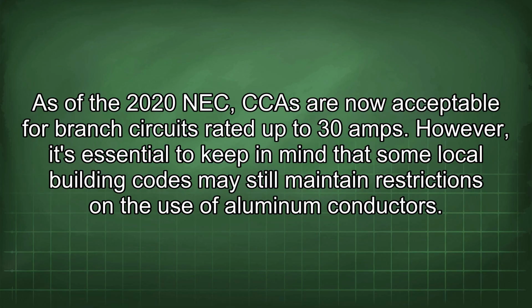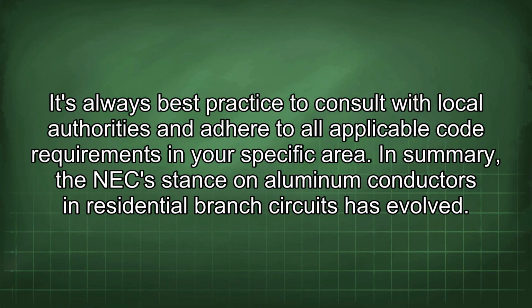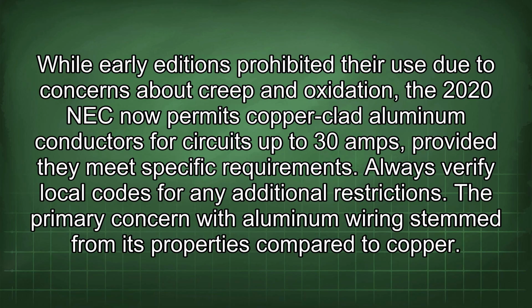However, it's essential to keep in mind that some local building codes may still maintain restrictions on the use of aluminum conductors. It's always best practice to consult with local authorities and adhere to all applicable code requirements in your specific area. In summary, the NEC stance on aluminum conductors in residential branch circuits has evolved. While early editions prohibited their use due to concerns about creep and oxidation, the 2020 NEC now permits copper-clad aluminum conductors for circuits up to 30 amps, provided they meet specific requirements. Always verify local codes for any additional restrictions.